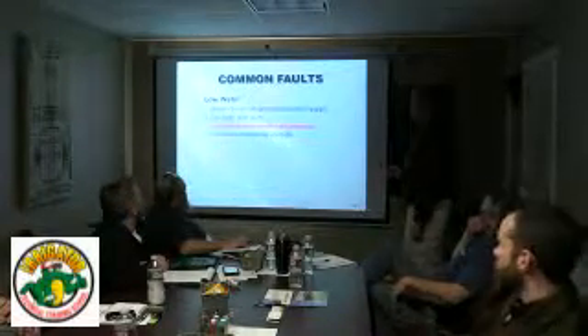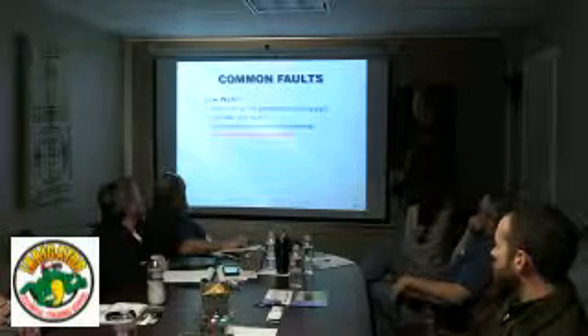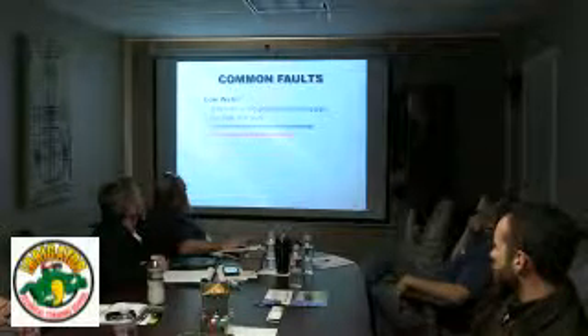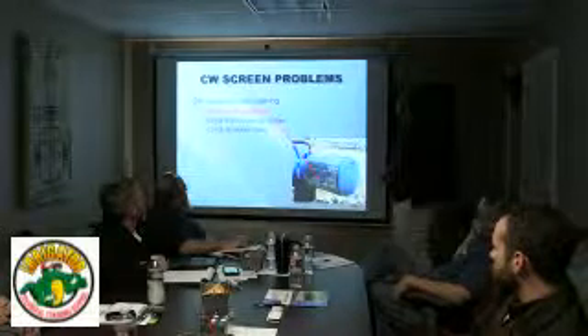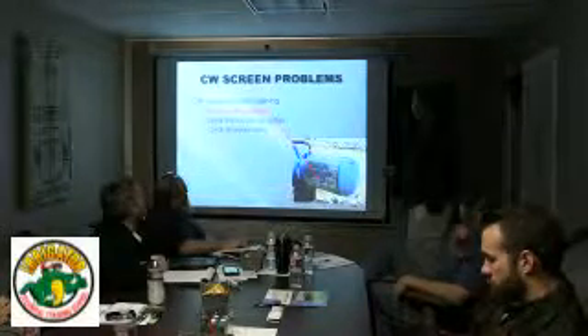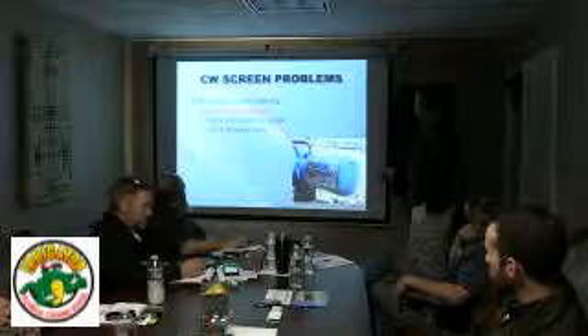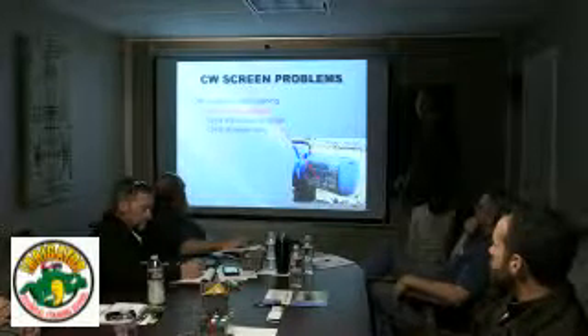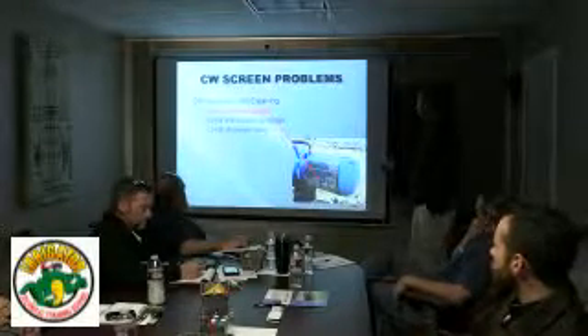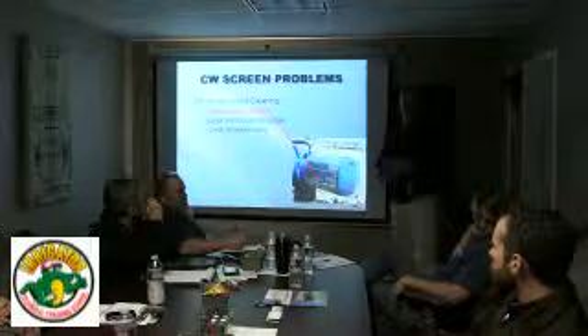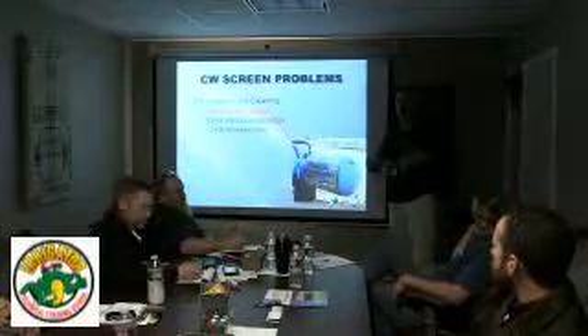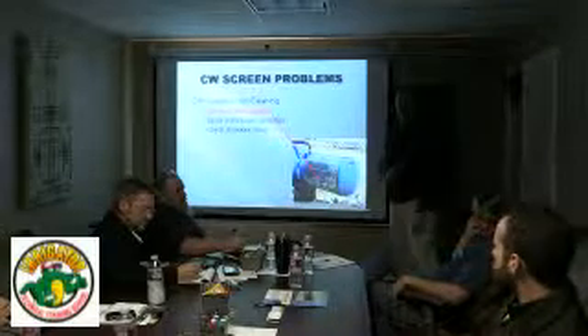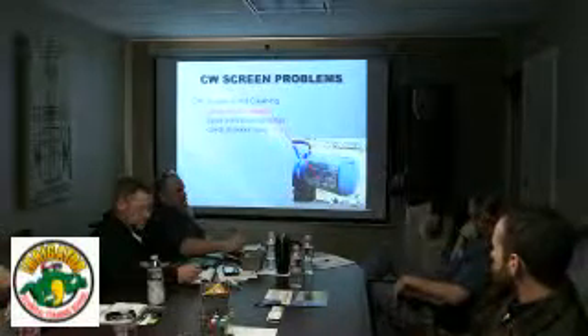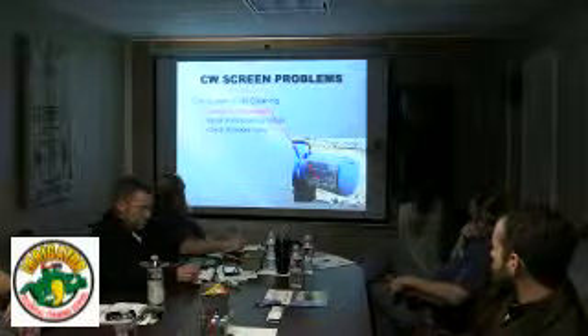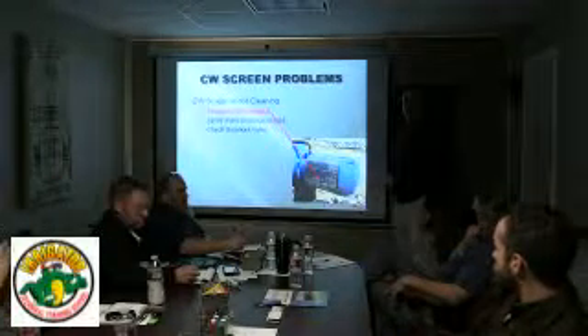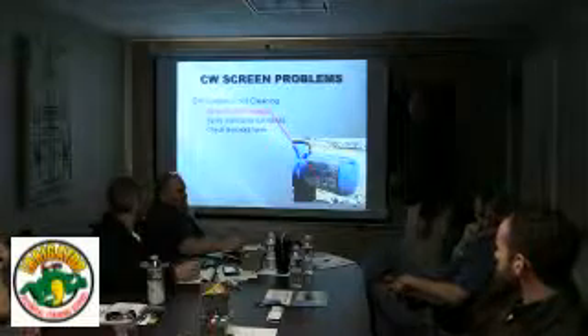Clear water, or CW, screen not working correctly, those can get plugged up. Some of the things that might cause that is the spray wands. There's spray wands right here and over here. The water pressure coming into here causes that to spin, and it forces the debris from the spray on the inside out away from the screen. If that's not spinning, that could cause not enough supply going through the screen, getting to the vault. That could cause a low water fault.